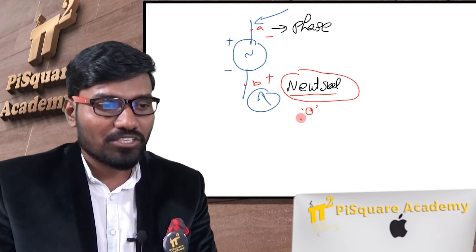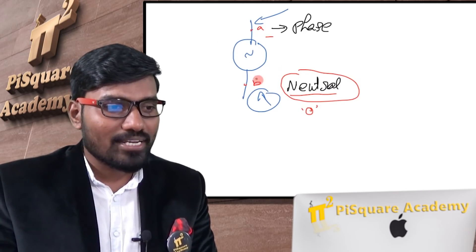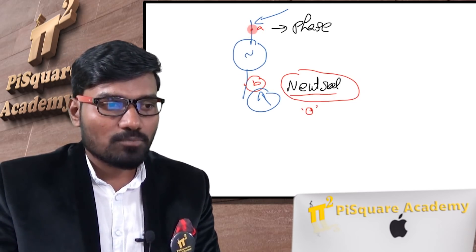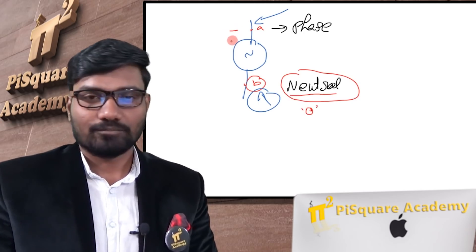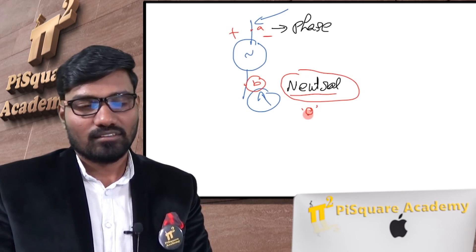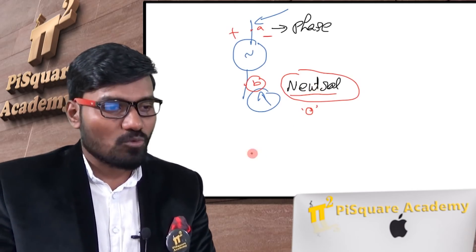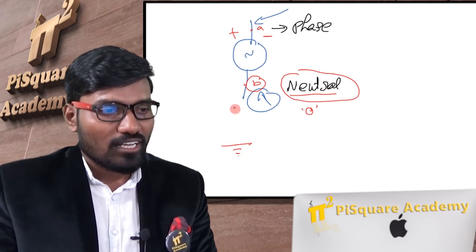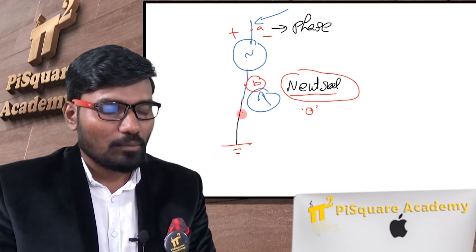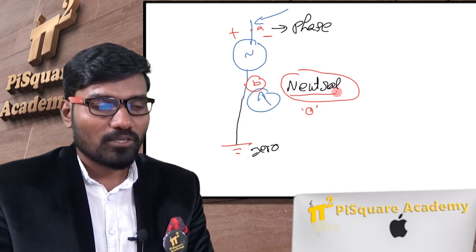Point B is always at zero potential. With respect to point B, the phase polarity will be positive in one half cycle and negative in another, but this neutral potential is always zero. Who is making sure that this potential is zero? That's what the ground does. By connecting this neutral point to the ground — which has zero potential — the neutral potential is maintained at zero volts.